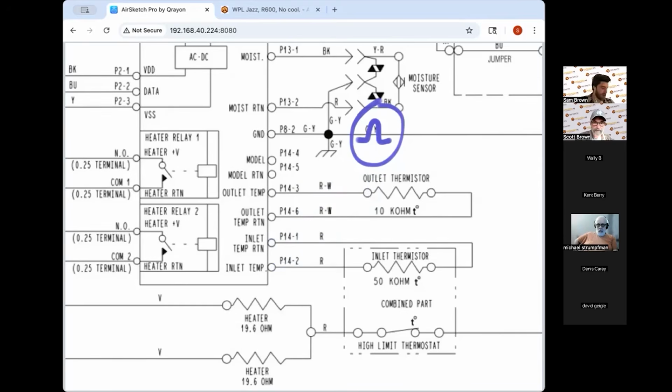Because you would have your voltage divider circuit in there, and you want to make sure you're not reading across that. If it's still connected, you're going to be reading whatever else is going on on the circuit board, or the voltage divider circuit, and it's all going to be in parallel with the outlet thermistor, as far as the way your meter is going to read it. So you want to isolate it. Get rid of any confusion factor like that, and just know what you're doing when you're making a resistance measurement and what component you're actually wanting to measure. You're not interested in what's going on in the circuitry on the board. You want to check the outlet thermistor, so isolate it.